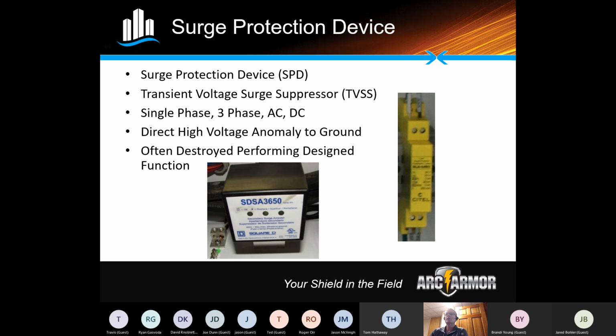These are some pictures of surge protectors. This first one that I'm highlighting is just a 3-phase Square D standard surge suppressor. The one here is a 4 to 20 on the side. That's a little blurry, but it's a 4 to 20 surge protector going on a 4 to 20 signal. So any questions on surge protection devices?